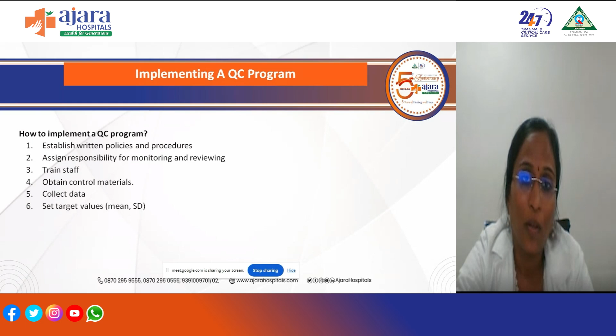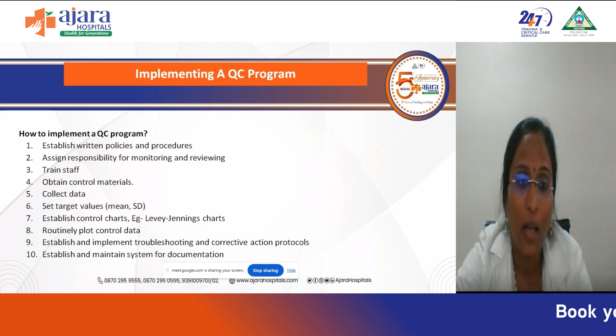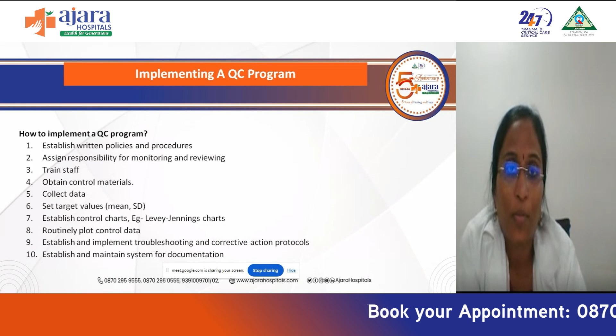So you should be able to establish your own controls, and also you should be preparing with the controls. You should be preparing with the LJ charts. So whenever there is a problem, you should be able to troubleshoot those problems. So if you have your data in your hand, you will be able to do that. Whenever you have your QC material, if there is any problem, if the control is not working, you have to follow this flow chart to have proper troubleshooting.